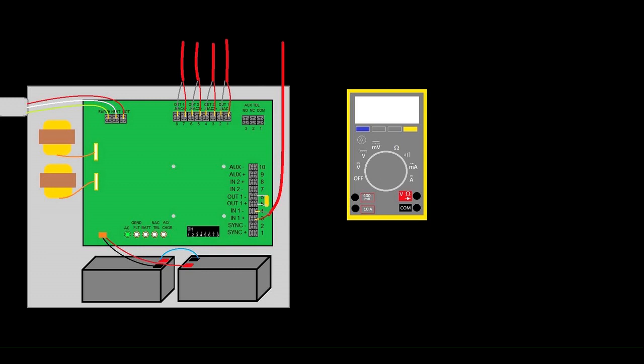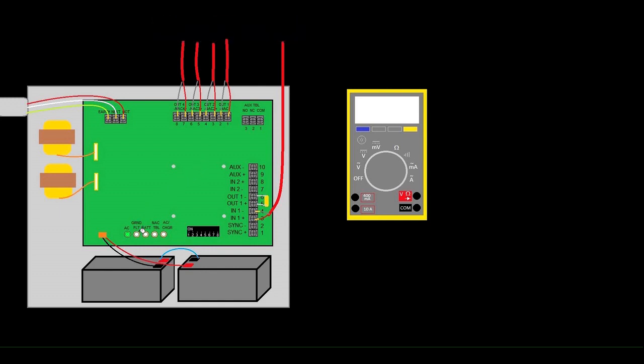Let's assume that what we have is an FCPS or a NAC extender or a power supply like we've looked at in the last few videos and it's got a ground fault on it. So we know that would show itself as this light. Anyway, so the ground fault light on the bottom would be solid.